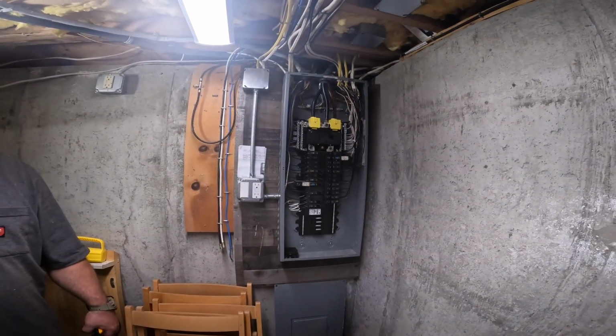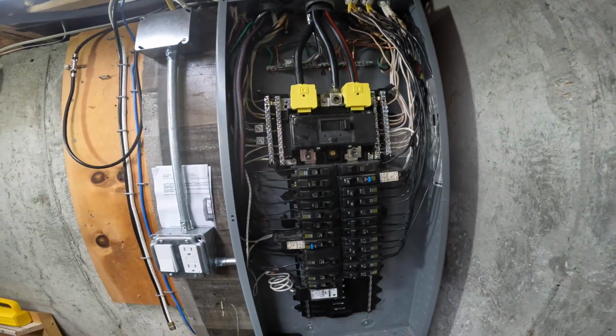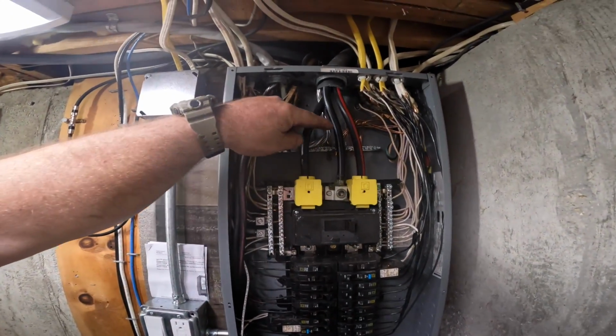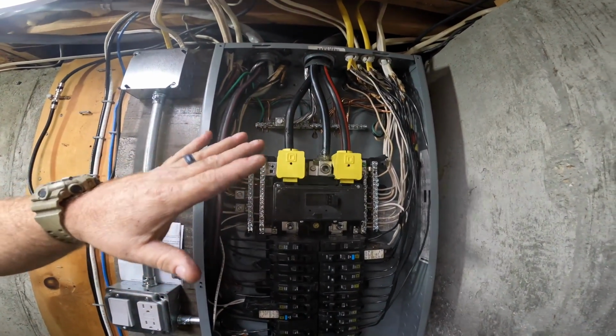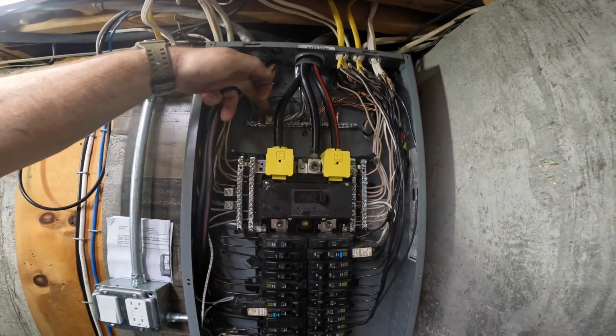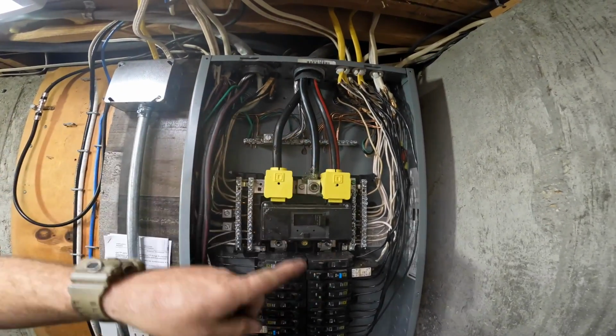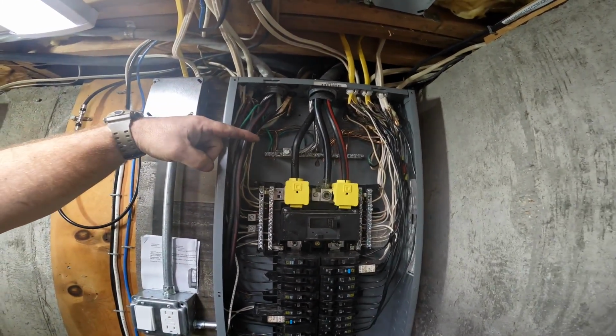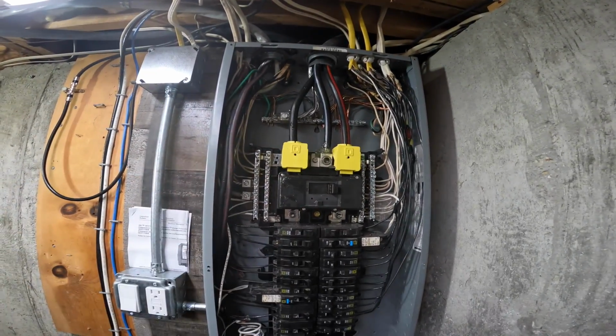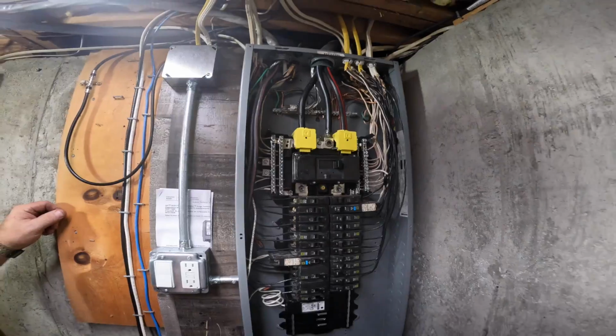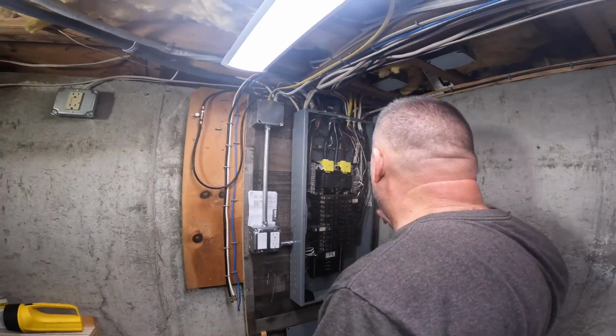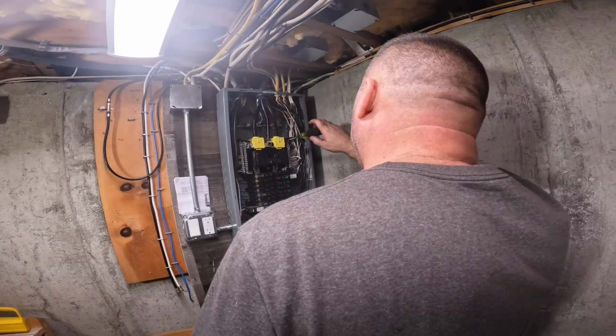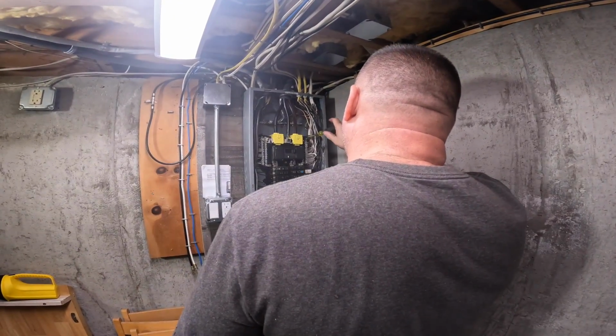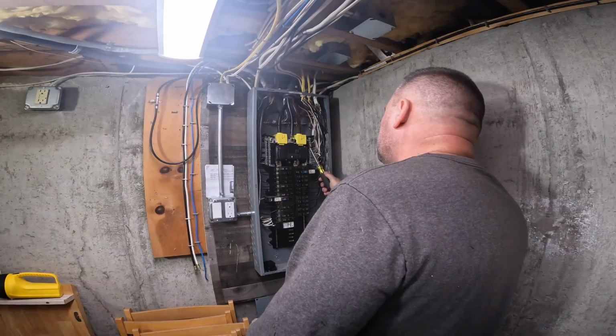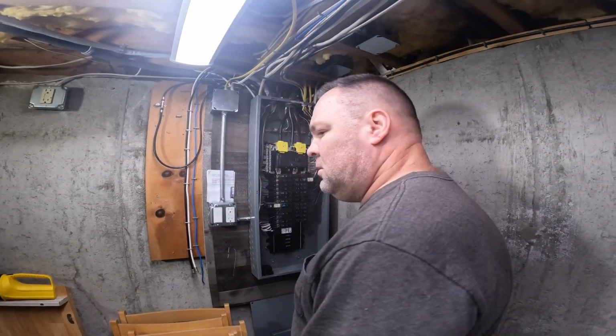Oh, transfer switch is in. Nice, huh? Very good. So as you can see inside the panel there, we changed the ground wire. The neutral just used to come in here, it was just a 3-wire. Now it's a 4-wire. Right. And that equipment grounding conductor goes right to this lug into the bar. And so each of the equipment grounding conductors from each circuit are now isolated from the neutral. I think I gotta pull, yes, I gotta take out the bonding screw here. Otherwise all that work is for nil. Now we're all set.